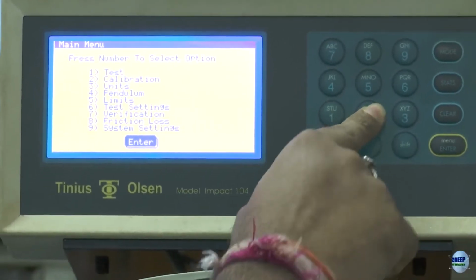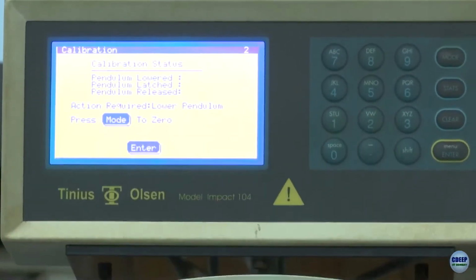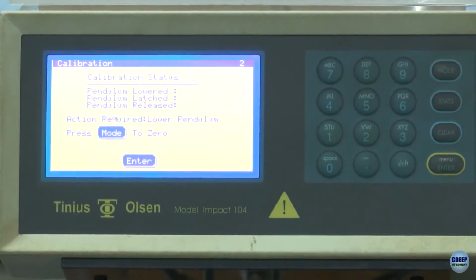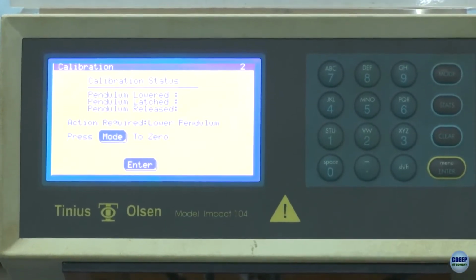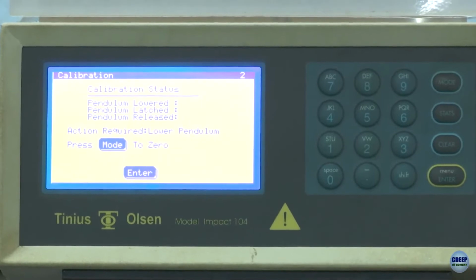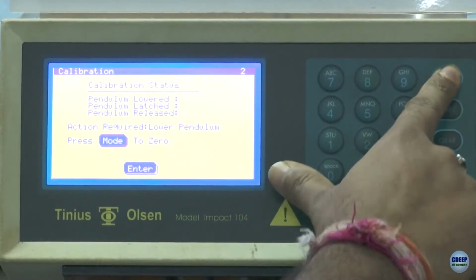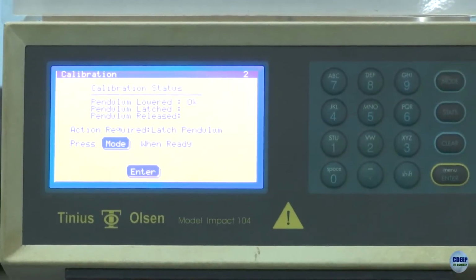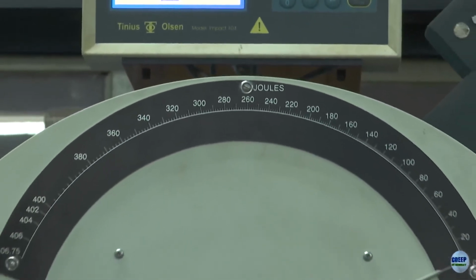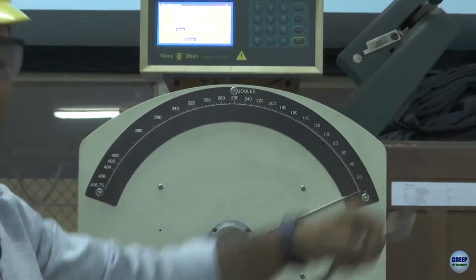First we will do the calibration, which is serial number 2. I will press serial number 2. The machine commands us on what action is needed, telling me to lower the pendulum. It is already lowered, so I press OK, then it asks me to latch. The remote control is in my hand, so I will press Mode and the pendulum will automatically go and latch at a particular height.